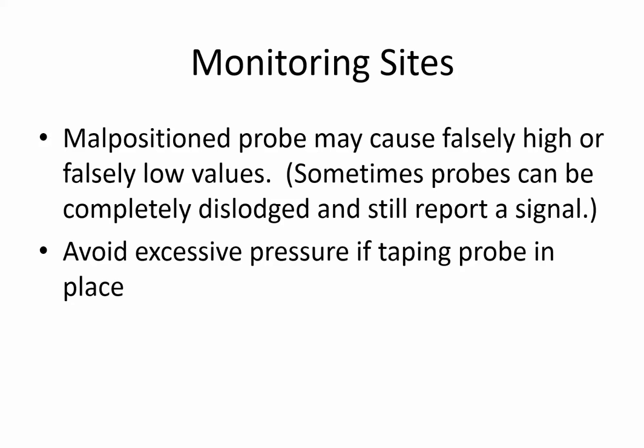In any site, a malpositioned probe may give falsely high or falsely low values. Sometimes probes can be completely dislodged and still report a signal. I walked into an empty operating room one time, and the pulse oximeter was showing a saturation of 80%. There was no patient in the room. There was nobody connected to the pulse oximeter. It was simply sitting on the bed. It was a pediatric probe, and it was reporting a saturation of 75%.